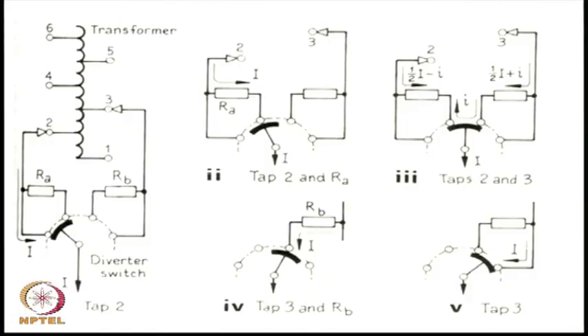The next figure shows how on-load tap changing can be arranged. So, this is, let us say, a particular winding of the transformer with 5 tap positions. Let us say once the connection was at tap 2, we want to go to tap 3. For onload tap changing, it has to follow a certain sequence. This is the selection switch. First the selection switch, which was at position 2, and each of these taps is connected with a current limiting resistance.